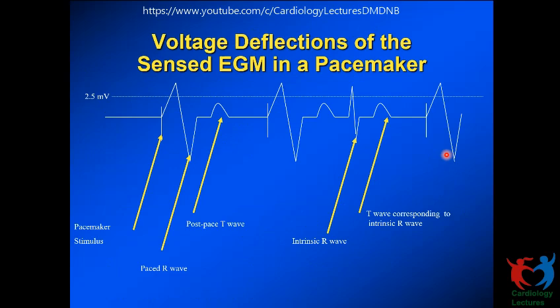Okay, so then we are stimulating and sensing, and in order to accurately sense, we program a sensitivity setting. Typically, it's about 2.5 millivolts in a ventricular pacing setting. In Medtronic, it is 2.8 millivolts. And if you don't do anything else and only rely on the sensitivity setting, then any waveform inside the heart with an amplitude bigger than 2.5 millivolts, the pacemaker is likely to sense. That means it can sense the pacing stimulus itself, because the pacing stimulus is 2.5 volts, which is 1000 times more powerful than 2.5 millivolts. So it is likely to sense that, and it might even damage the pacing circuitry, because my sensing circuitry is designed to handle millivolt magnitude waveforms.